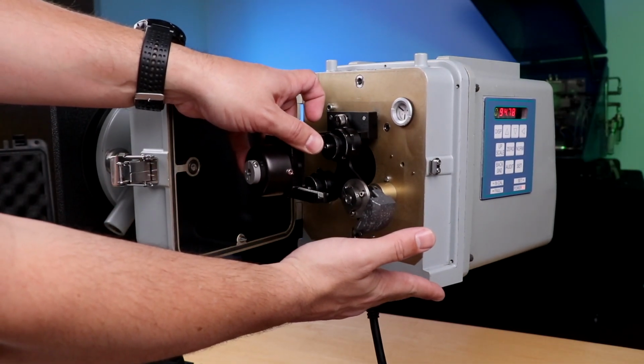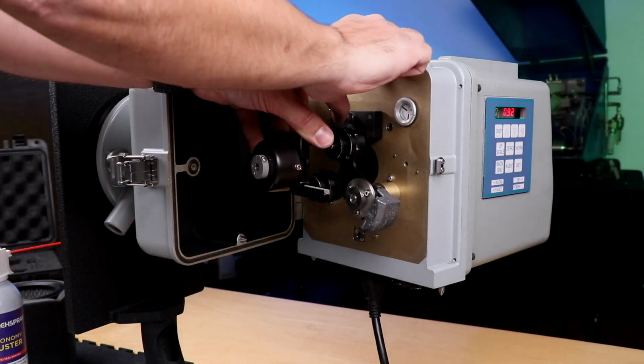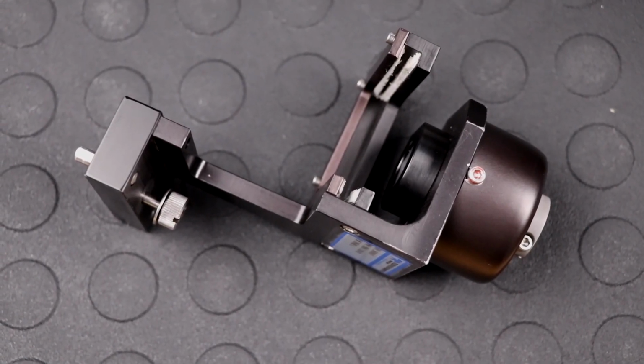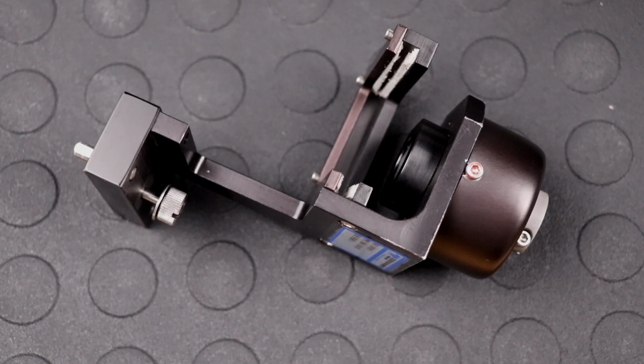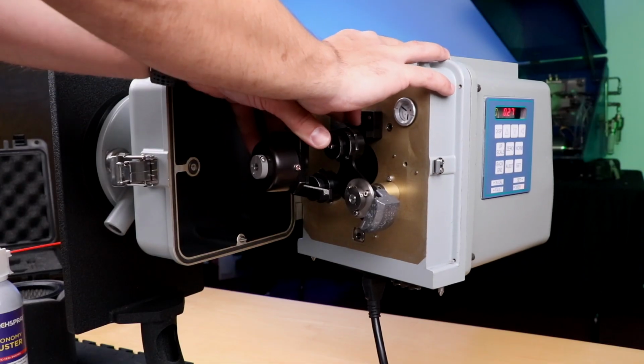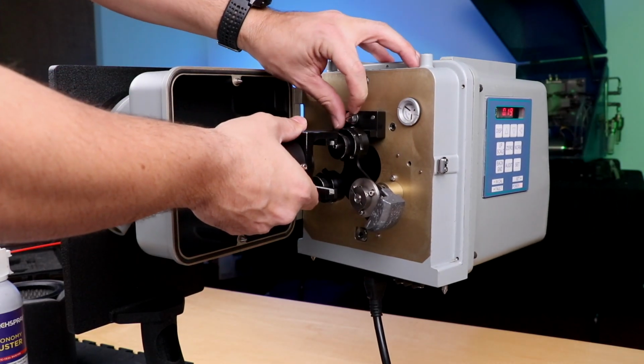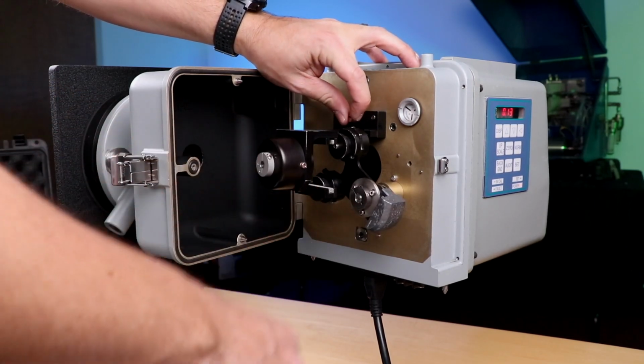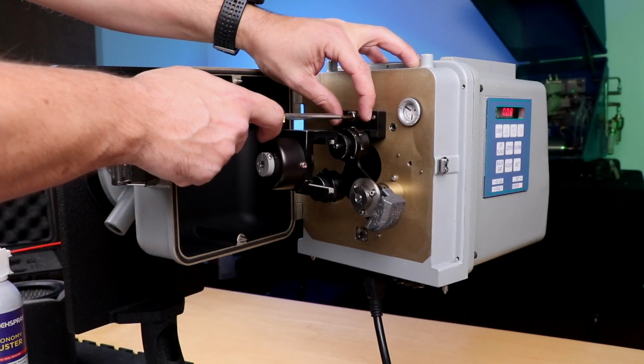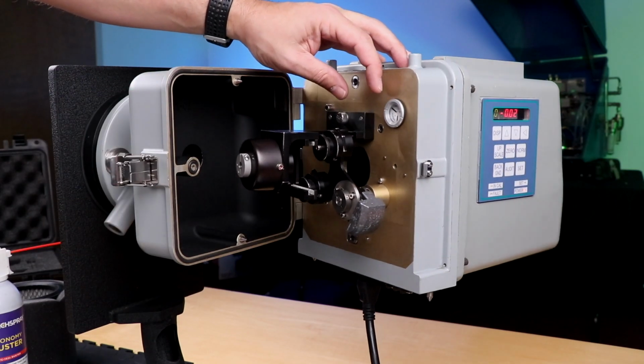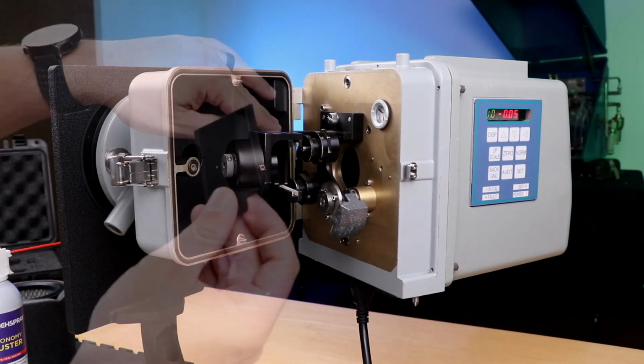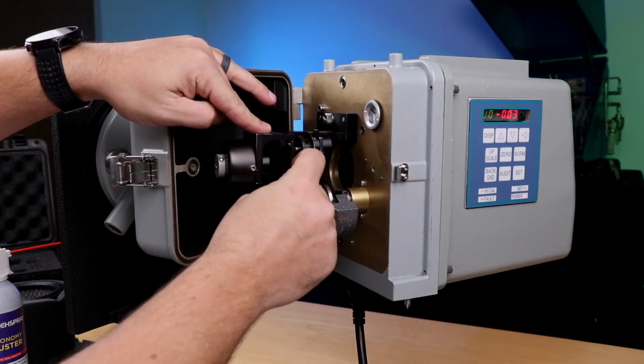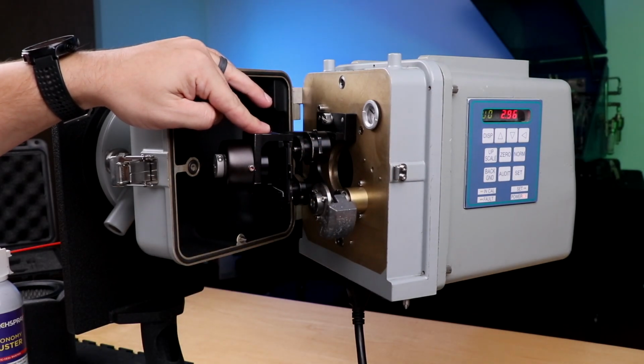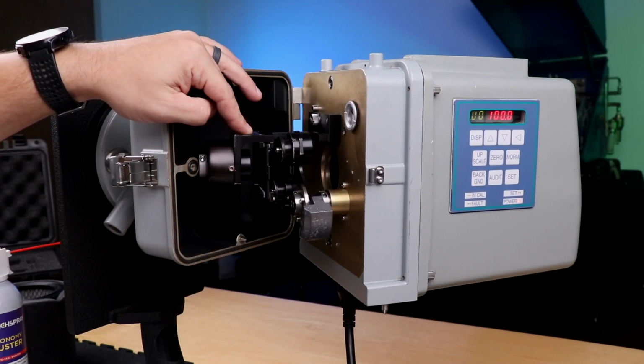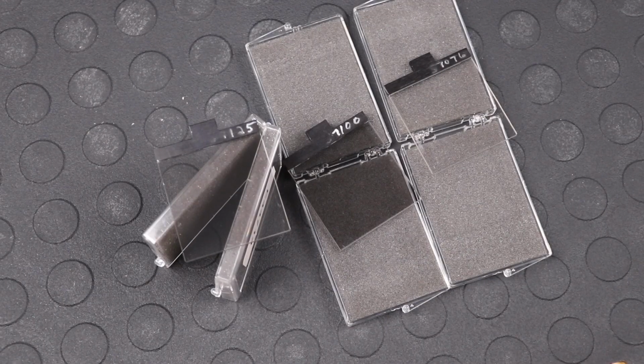Last, the calibration kit mounts in front of the exit window when performing maintenance or audits. Each calibration kit is unique to the monitor. It is adjusted during an off-stack calibration to simulate the sample path, or 0% opacity. 100% opacity, or the background, can be achieved by inserting a blocking plate into the filter slot. The filter slot is also used to house the NIST certified neutral density filters during a quarterly audit.